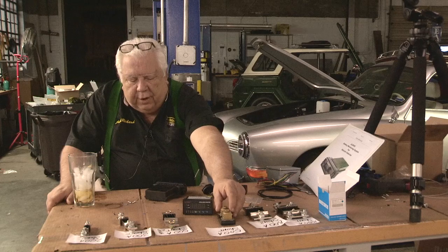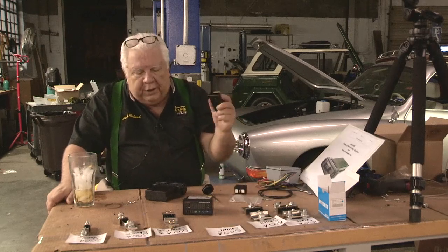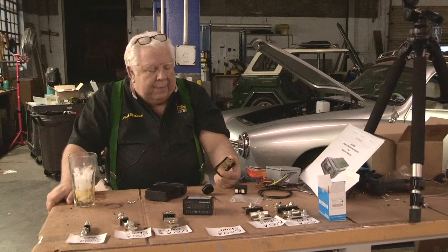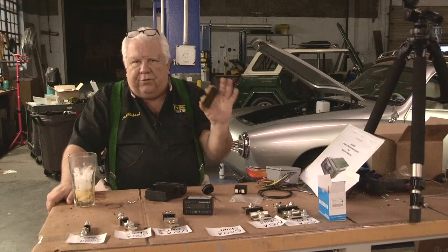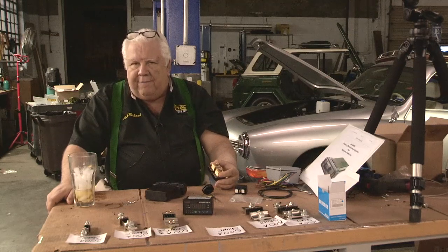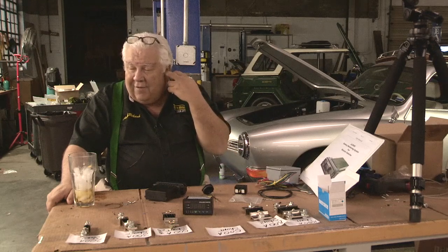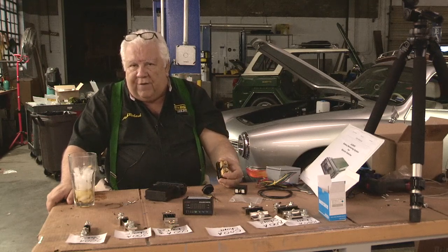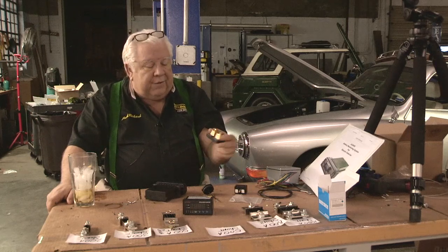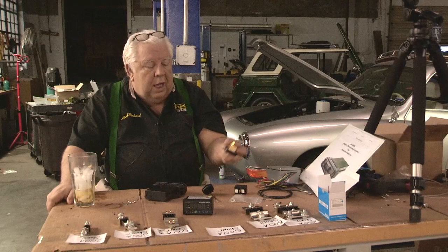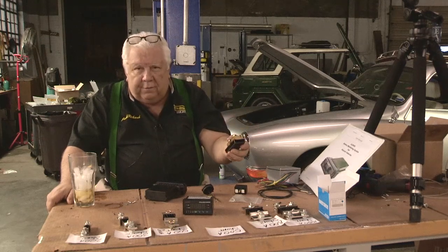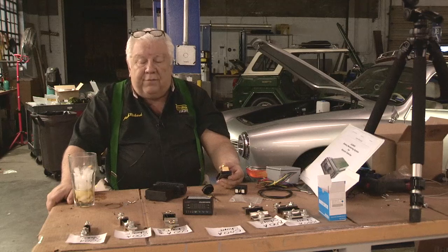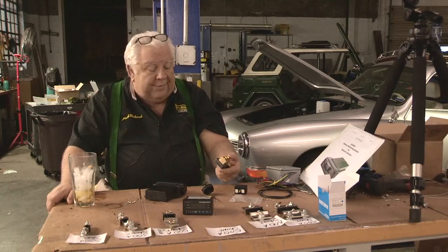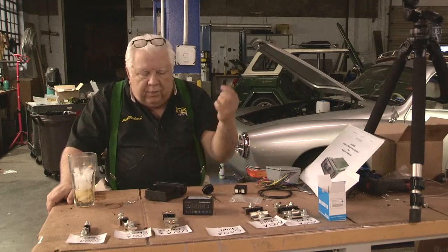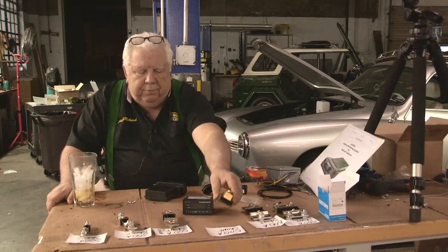Well, here's a 500 amp shunt, but it's 50 millivolts. Can you use that with a JLD505? Absolutely. This is real simple. If it puts out 50 millivolts at 500 amps, how many amps are we talking about for 75 millivolts? Well, 75 is 1.5 times 50. 1.5 times 500 would be 750. This is exactly the identical resistance that a 750 amp 75 millivolt shunt would be. It's just marked 500 amp, 50 millivolt. The resistance is exactly the same.